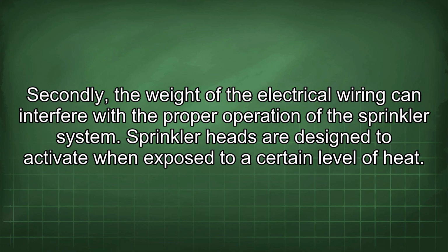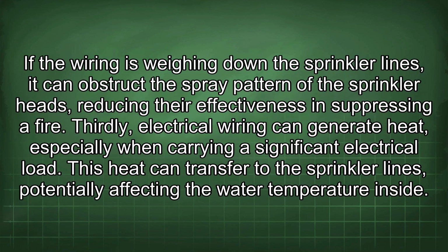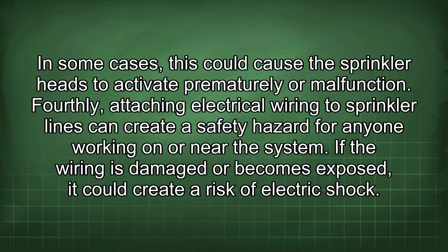Secondly, the weight of the electrical wiring can interfere with the proper operation of the sprinkler system. Sprinkler heads are designed to activate when exposed to a certain level of heat. If the wiring is weighing down the sprinkler lines, it can obstruct the spray pattern of the sprinkler heads, reducing their effectiveness in suppressing a fire. Thirdly, electrical wiring can generate heat, especially when carrying a significant electrical load. This heat can transfer to the sprinkler lines, potentially affecting the water temperature inside. In some cases, this could cause the sprinkler heads to activate prematurely or malfunction.